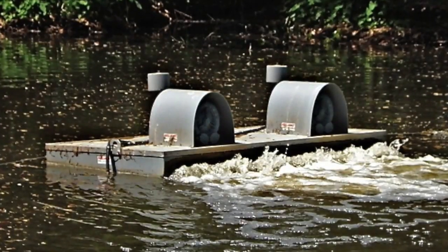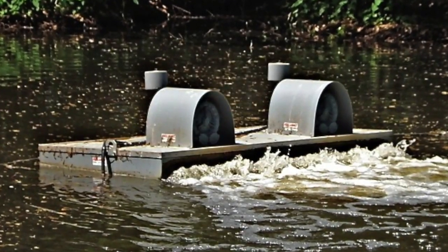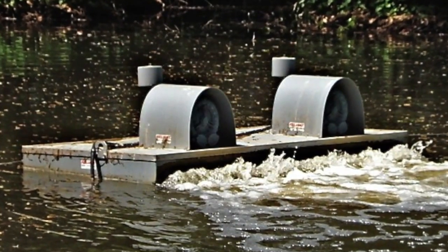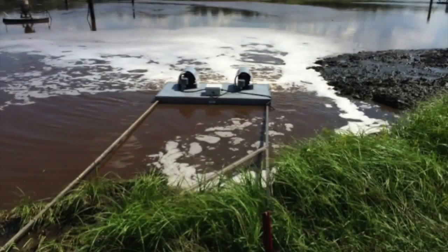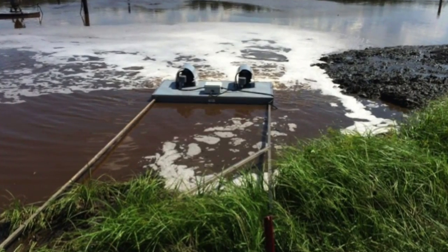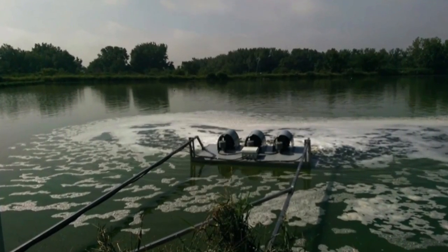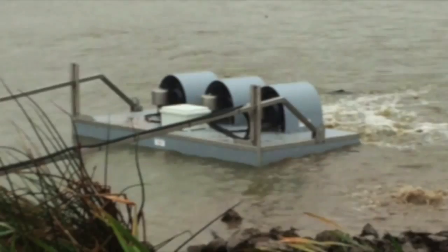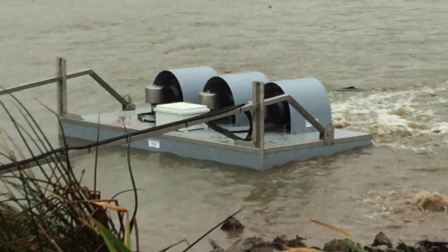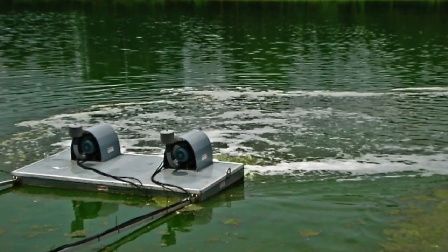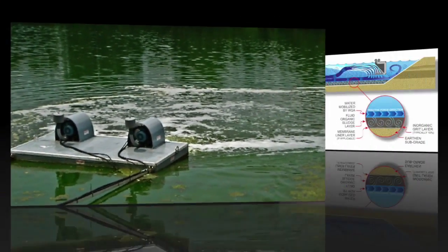The lagoon aerator provides over 15 pounds of dissolved oxygen per hour, or 3.87 pounds per horsepower hour, to the water. It utilizes only 4 horsepower, or 3 kilowatts, to perform this unique capability. This aerator utilizes the weight of slow-moving water at the sludge level to continually roll water along the lagoon bottom, thereby eventually raising the sludge blanket enough to activate it.